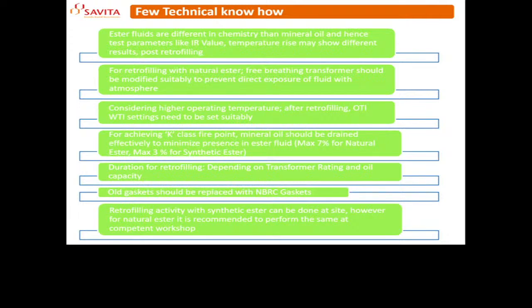Now let us see some technical know-how on how to do it. You can do it at site when using synthetic ester fluid with adequate infrastructure. For natural ester fluid, the condition is that you have to use it in a sealed transformer, you cannot use it in a free breathing transformer. So if your transformer is not sealed, you have to make arrangements, and it is better to do it at the nearest workshop.